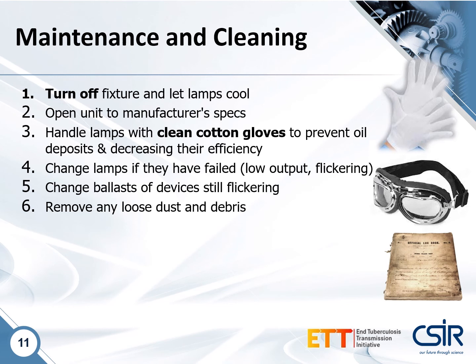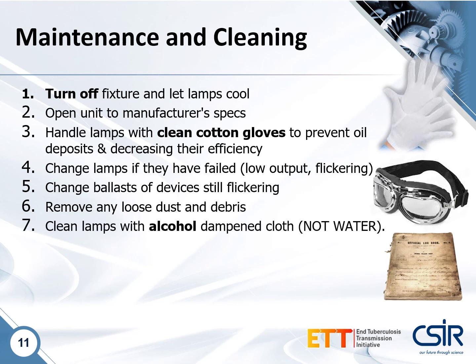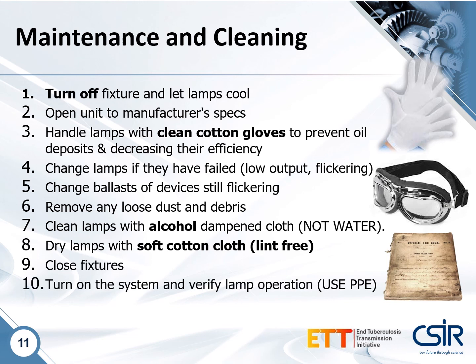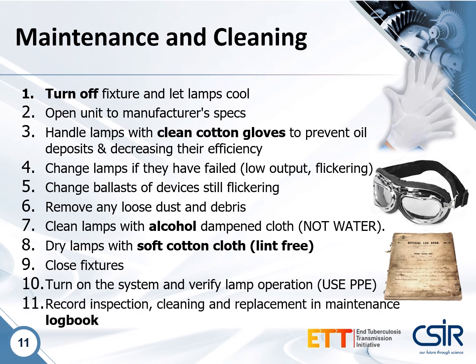And then you also want to remove any loose dust or debris from inside the device before you do any wet cleaning. Wet cleaning of the lamps, for instance, is done with an alcohol dampened cloth. Do not use water. Water, and especially soapy water, can leave residues on the surfaces, reducing efficiency and output. And then you want to dry the lamps with a soft cotton cloth. Use lint-free cloths. You don't want to leave any debris inside the device. Close up the fixtures, and then making sure that you have not forgotten to put on your PPE, turn on the system and verify lamp operation. If there are any problems with the system still, like the flickering lamps, you might want to go back into the device to make any further necessary repairs or replacements. Then record your inspection and cleaning and replacement in your maintenance logbook.